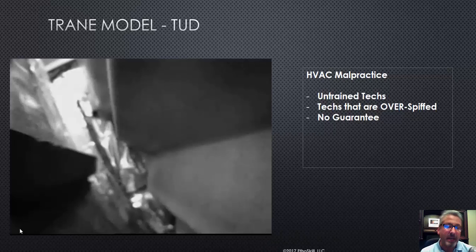So the homeowner did say, according to them, that the contractor or technician said you have a cracked heat exchanger and you could get carbon monoxide, so shut it off. Now, what stimulated this call was a no-heat situation, and it was actually an ignition module failure.